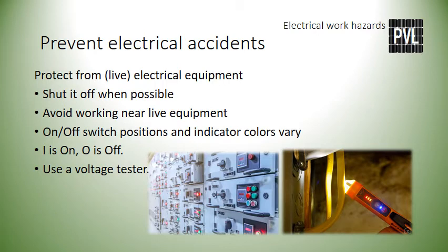Switch location and styles may be different in different equipment. Don't rely on labels, indicator light colors, or switch orientation to determine if equipment is operating. Manufacturers may use any color to indicate on or off status. The international symbol for on is the '1' or 'I', and for off is the '0' or 'O'. But always ensure that equipment is off by means other than the state of a switch or indicating light, because those can easily fail. Using a voltage tester can determine if equipment is getting power by checking its wiring.